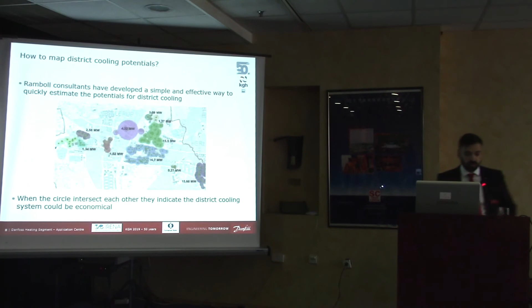Regarding equipment, district cooling requires the same equipment as district heating. There is usually an interface in the building, typically a district cooling substation. At Danfoss we have a lot of experience with district heating substations, and this experience transfers to district cooling. The principles are the same, but there is a higher need for precise control since we are working with low delta T's.